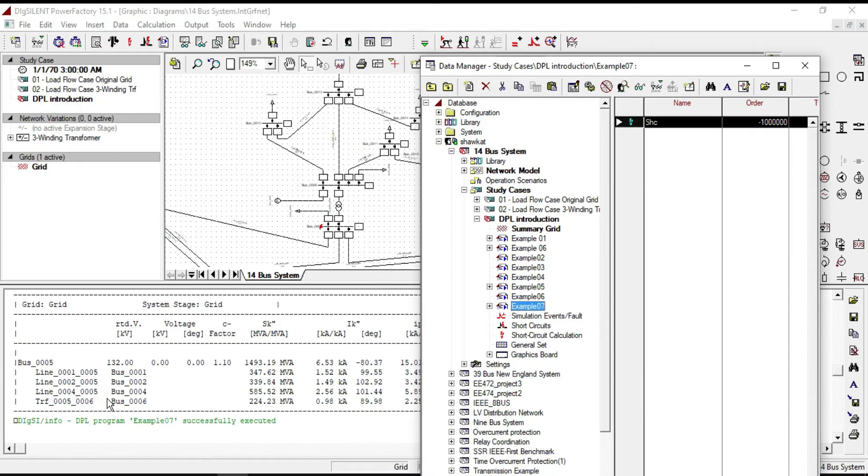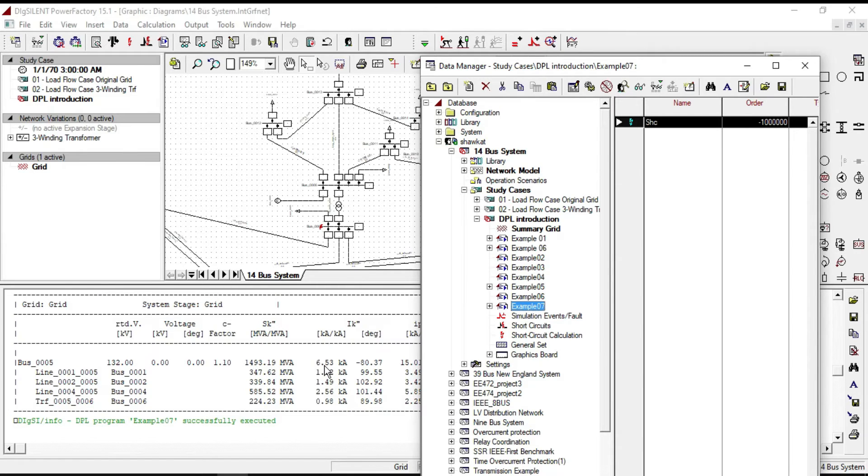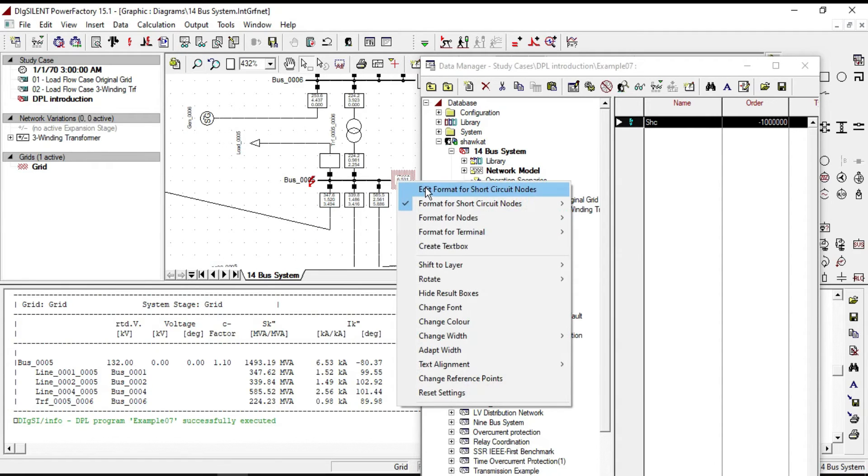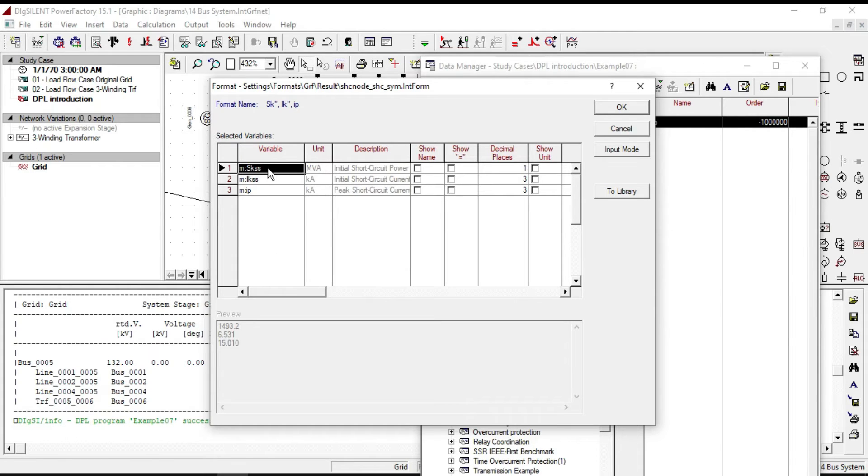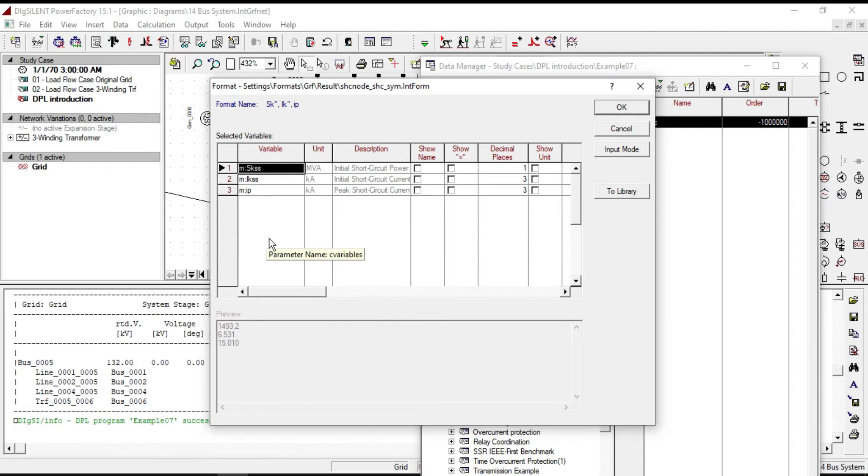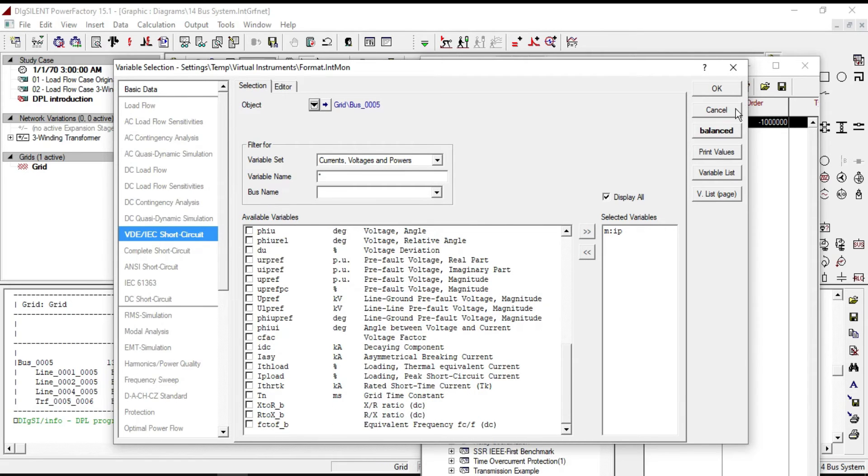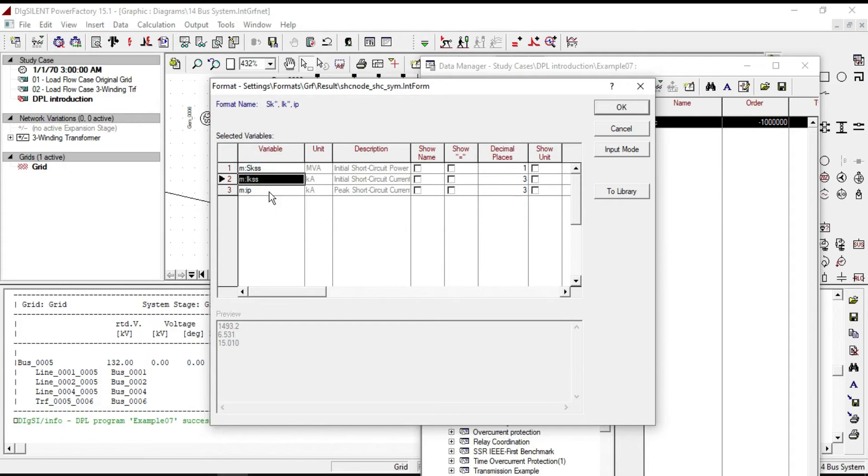In the output, if you want to get only the data of bus number 5, for example initial short circuit power and initial short circuit current, to access into parameter names, right click on bus number 5 and click on edit format for short circuit nodes. Here you will see the parameter name of variables. If you want, you can access to more variables by double-clicking here. As an example, I want to access to initial short circuit power and current.